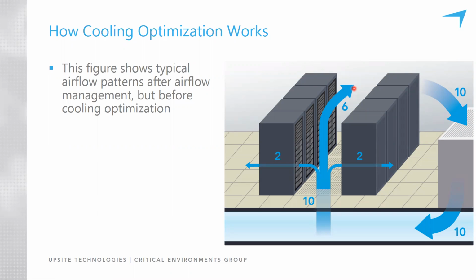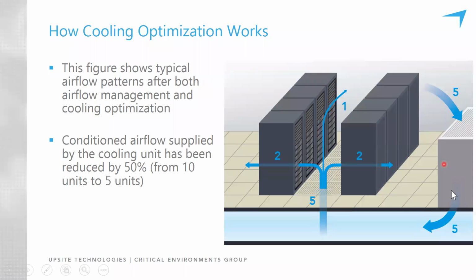So this does create the opportunity to optimize. We can now reduce the total amount of air moving through the room by reducing fan speeds. It's better to run 10 cooling units at half speed than it is running 5 cooling units at full speed. There's greater energy savings by doing the 10 at half speed, by the way. So we can reduce the total amount of air moving through the room and now supply, say, 5 units of air into a cold aisle where 4 are needed. We've got 1 unit of extra air to maintain a little positive pressure and accommodate for some variations in flow rates through the IT equipment.